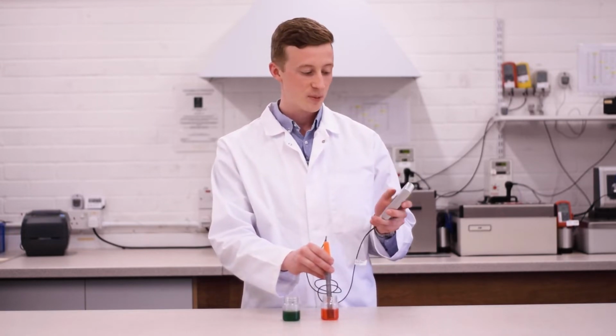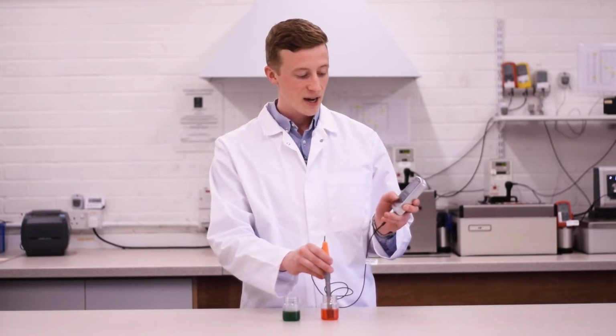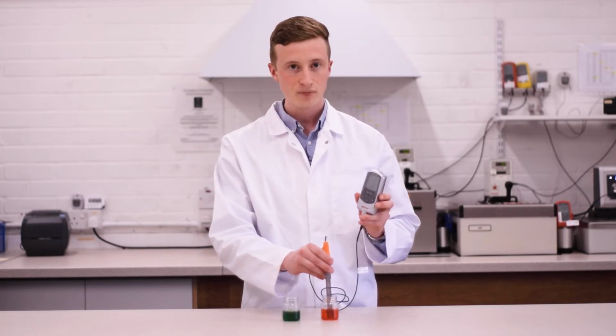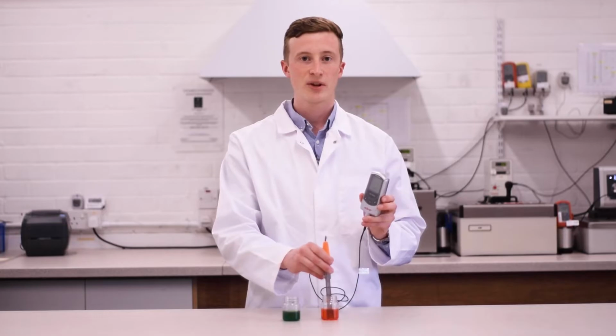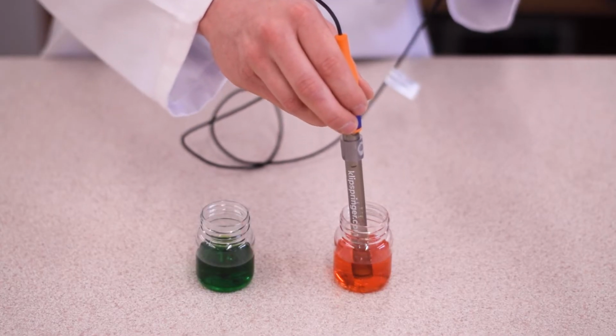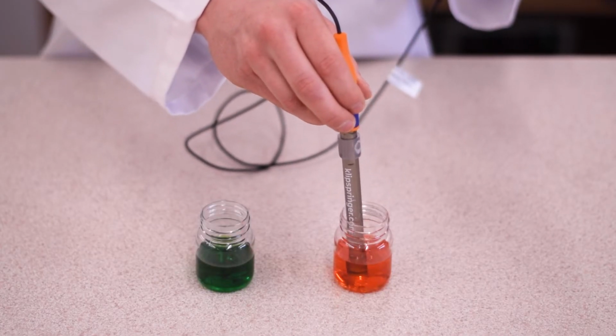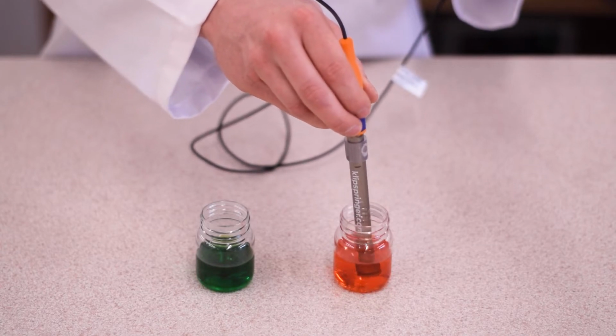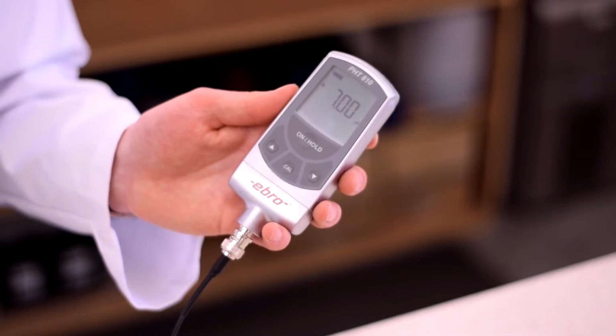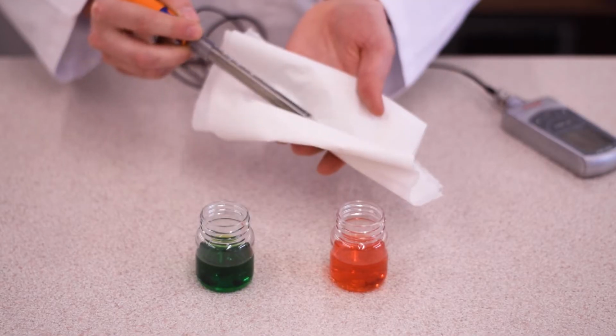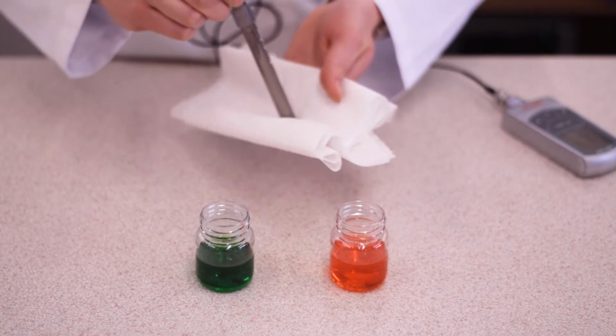Cal 1 will be displayed. Press cal again to confirm. Begin calibrating by stirring the electrode in the buffer solution. When the display shows OK and changes to cal 2, remove the electrode and dry it using a soft paper towel.